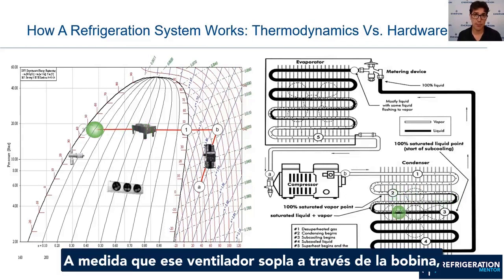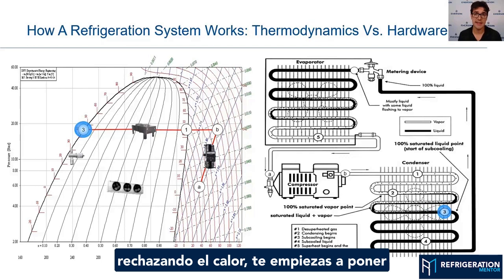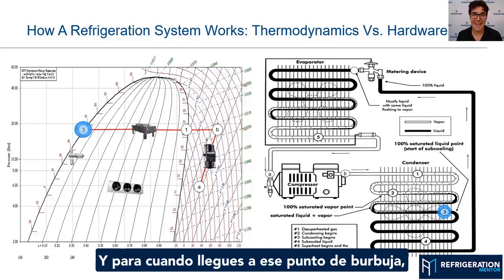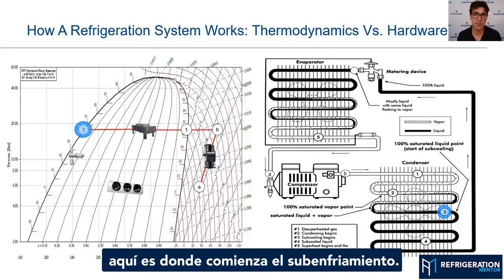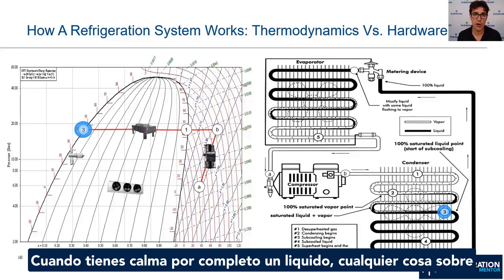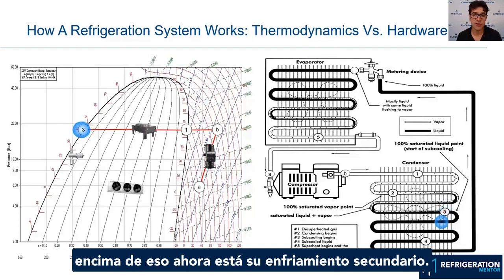As that fan blows across the coil, rejecting the heat, you start to get more and more condensing happening. And by the time you hit that bubble point, this is where your subcooling begins, when you have a full column of liquid.